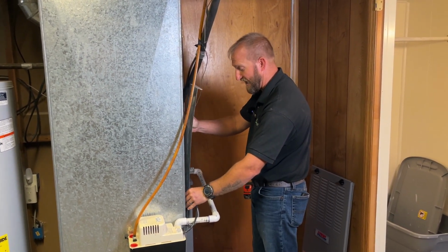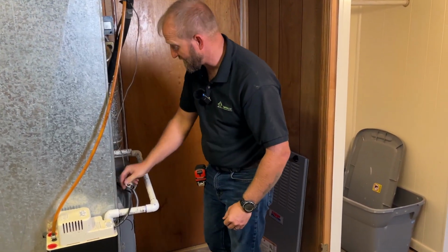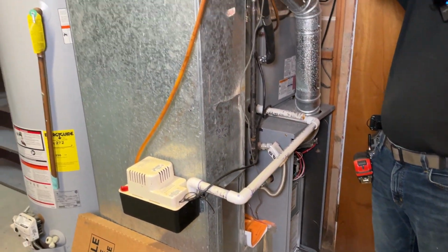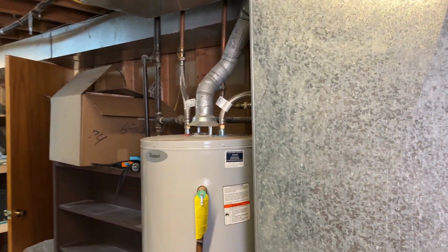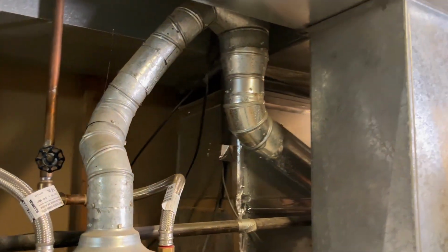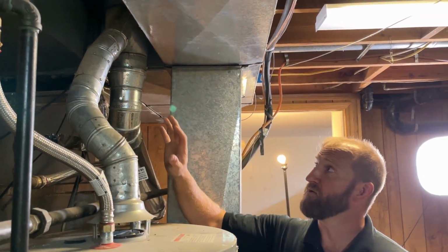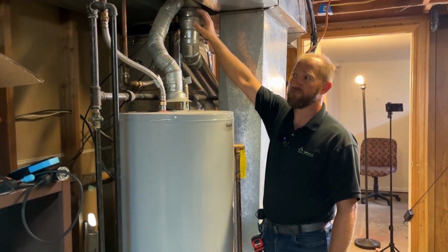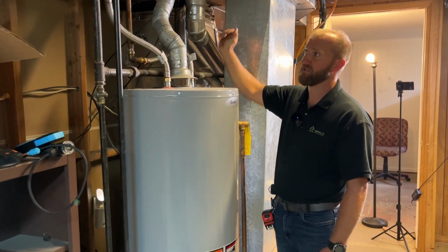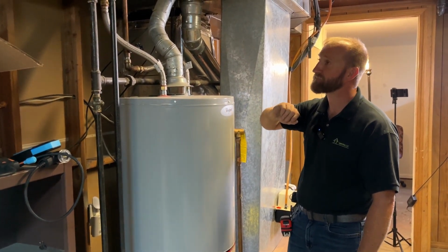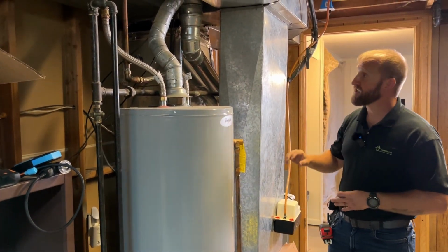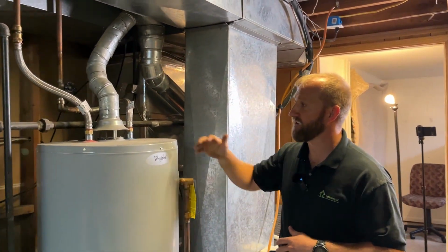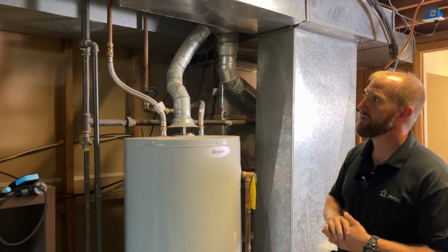We're going to look at the age and condition of the different appliances, like the furnace. Make sure that the flue is vented with a minimum 1/4 inch rise per foot for the furnace and for the water heater. When you have them joining up like this, your lower BTU unit should be venting above the higher BTU unit to prevent backdrafting. Another thing that you're going to look for is your water lines. Are they insulated? Is there any evidence of backdrafting from your water heater?